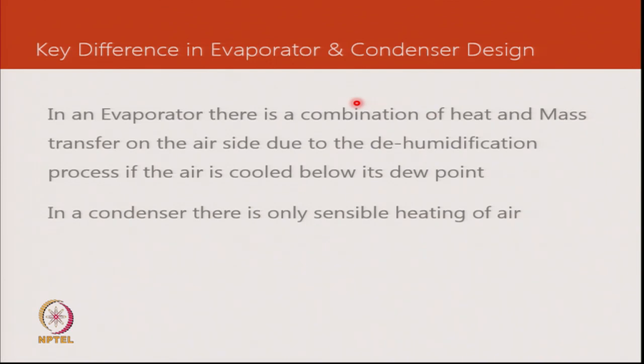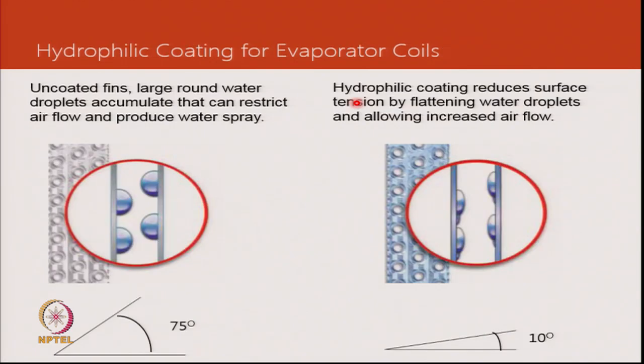Now, I will go into a little bit about the coating, which is different for condensers and evaporators. So to differentiate the kind of coating that we use, the one purpose of coating is to enhance the life, which means fins don't crumble when they are in corrosive environments. And we could do that by using stainless steel or copper with tin coating, or we could use aluminum with some special coatings. So, one such coating which is used on evaporator coils, which does a combination of things.